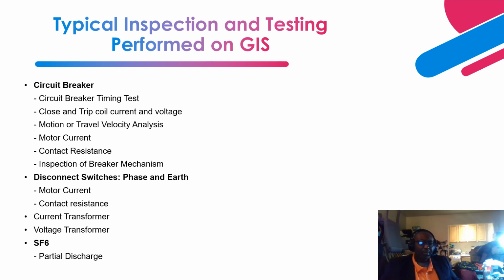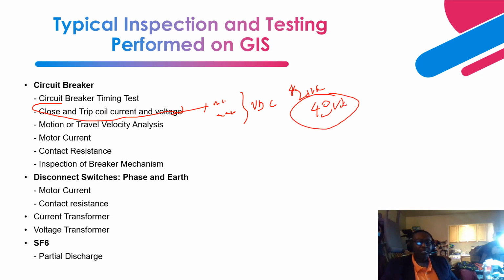But remember, there's a minimum and maximum voltage. Let's say a DC voltage is applied to operate the close and trip coil. If you have a substation with a 125 volts DC battery voltage that provides voltage to the close and trip coil, or a substation that has 48 volts DC, there's a maximum and minimum point that these coils are tested to, to make sure they at least pick up above the minimum, because that guarantees reliability to be in service and to operate reliably when in service.